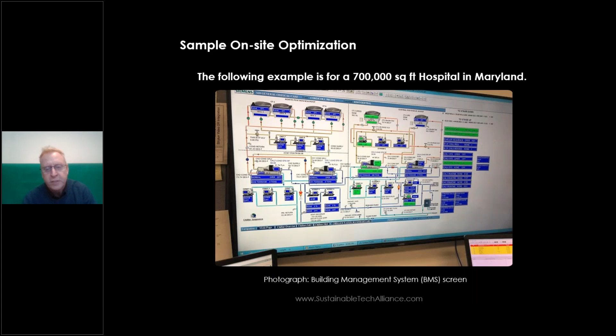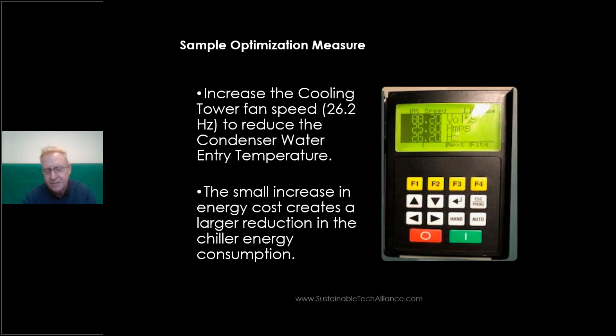What we saw, and I was personally on site for this one, is that they had about a 72-degree day and they were targeting about 68-degree indoor temperature. They were not running their cooling tower to full capacity, but they were putting stress on the chiller at an unnecessary level. So by increasing the cooling tower fan speed, we could reduce the condenser water entry temperature. And that small increase in the energy cost created a much larger reduction in the chiller energy consumption, because about 70% of energy consumption in chillers is in the compressor.